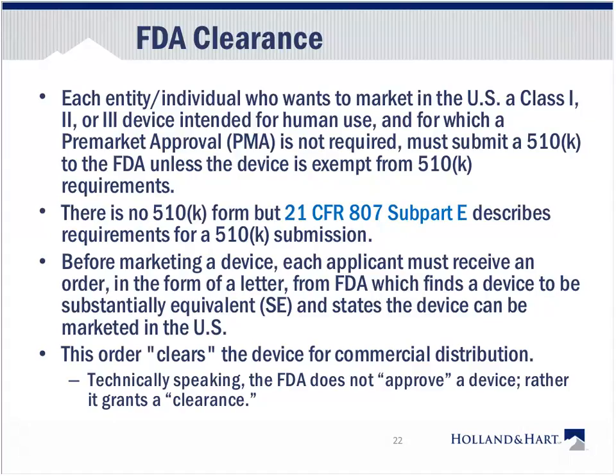So the FDA does not technically approve a medical device or other medical product. It clears that device. And so what happens is, if you are required to go through the 510K process, you submit an application to the FDA and you get back a letter from the FDA saying this medical device has been cleared for market. And it is literally just a form letter, but that is the way it works. Again, we don't talk in terms of approval, we talk in terms of clearance.